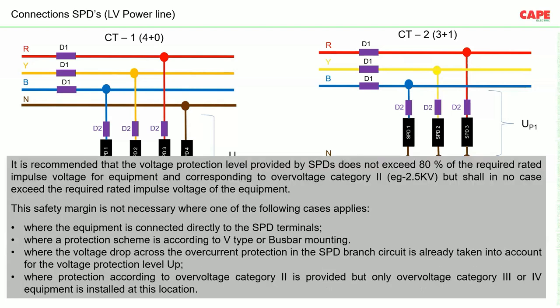It is recommended that the voltage protection level provided by the SPD does not exceed 80% of the required rated impulse voltage for the equipment. For example, if the impulse withstand voltage is 2.5 kV, the effective voltage protection level of the SPD should not exceed 2 kV. This is called the safety margin.